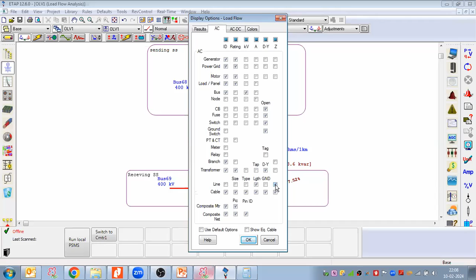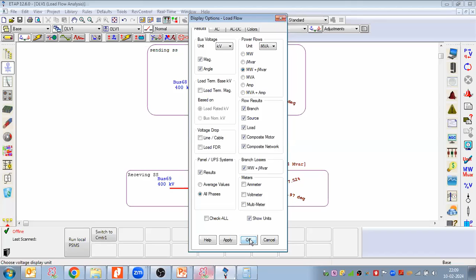One important thing I want to explain: length is important, other things are not important for now, so I uncheck these boxes and click OK, just to show the line length here. Now let me check the voltage, changing the unit from percentage to kV, so I can see the value directly instead of as a percentage increase.